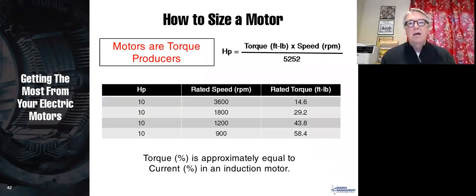Now, how should you size a motor? Well, motors are sized by torque. All motors are torque producers. Of course, this is true mostly after the motor has come up to speed, and your horsepower is equal to the torque times the speed divided by 5252. So all 10 horsepower motors are not the same. A 10 horsepower 3600 RPM motor is rated for 14 foot-pounds of torque, an 1800 RPM motor, 29 foot-pounds of torque, and so forth.